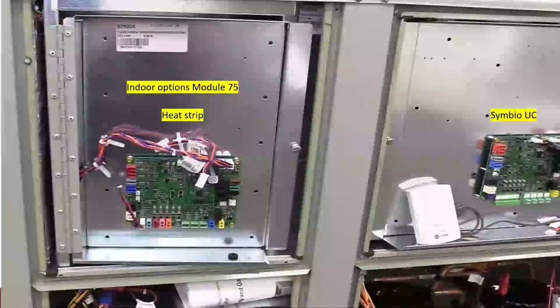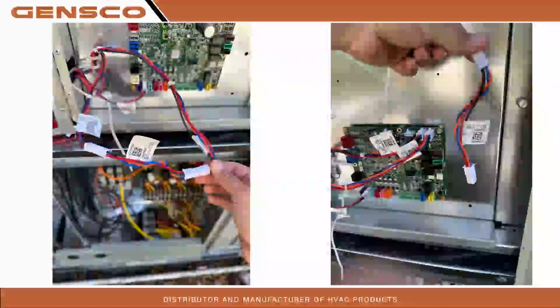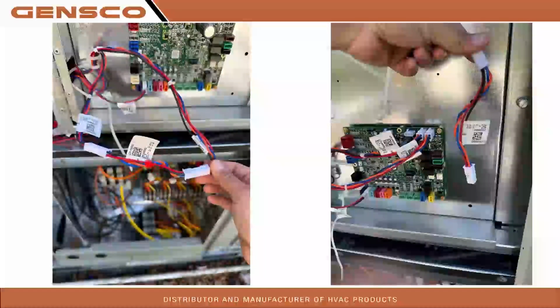I'll show you. So here's our indoor options module. Here's our heat strip down here. Here's where our electric heat connections. Remember that? That's where our electric heat connections land. This is just a temporary zone sensor they had on. There's our 700, right? So it's coming through power. Here's that harness that I was showing you earlier. If you don't have options module set, you're going to remove that and go ahead and plug it right in. Again, here's our electric heat connections.